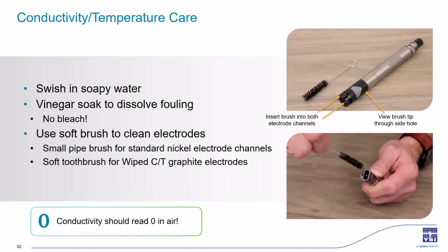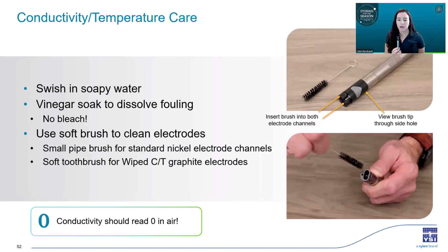So for standard CT sensors with nickel electrodes, like the ProDSS CT sensor that I have here, you can clean these electrode channels with a small pipe brush that comes with the sensor. Just insert the brush into each of the 2 channels, clean them gently with small strokes, and then rinse them well. And if you have an EXO wiped CT sensor, which has graphite electrodes, you can use a soft brush or a toothbrush to clean the prongs. After it's clean and dry, when you test the sensor in air, it should read 0. That's a good indicator that you've cleaned it well.